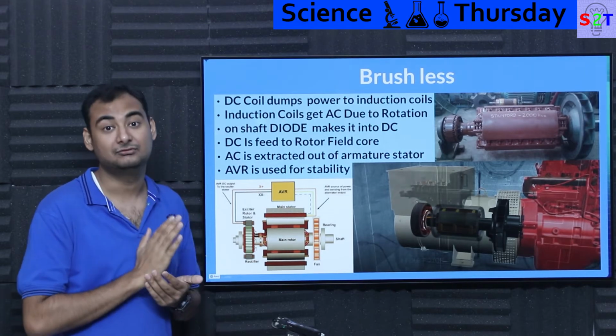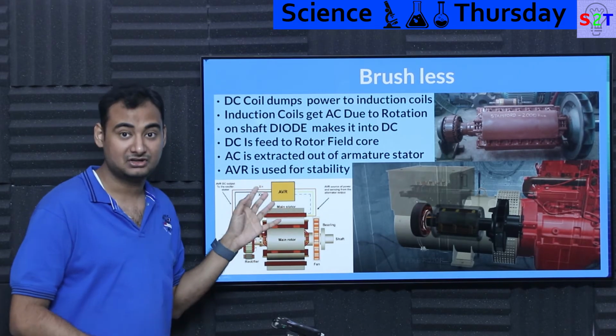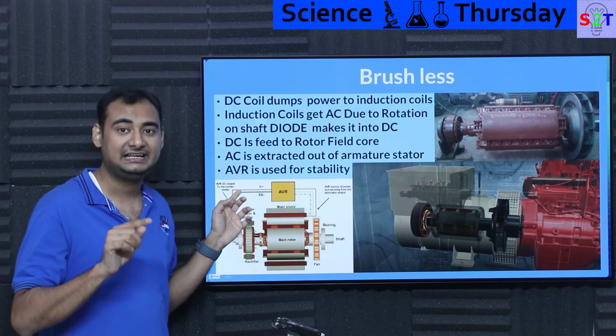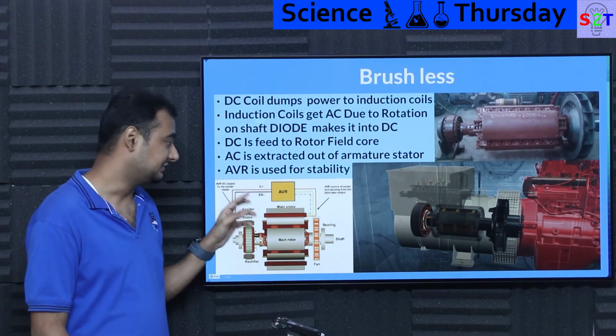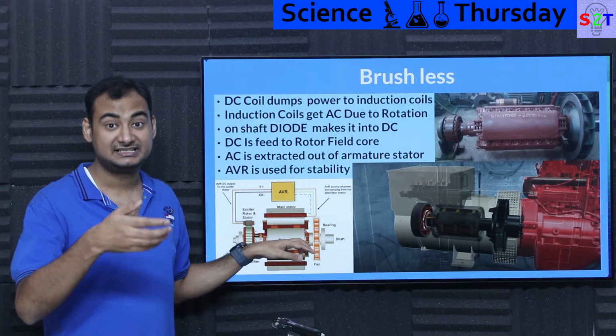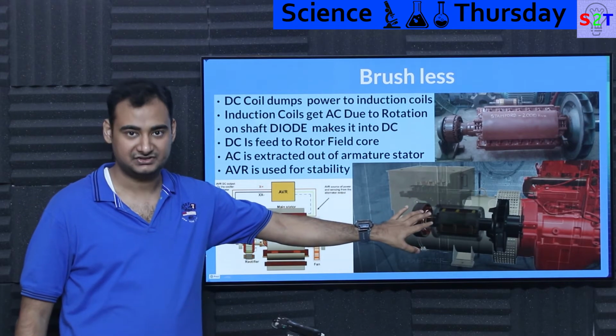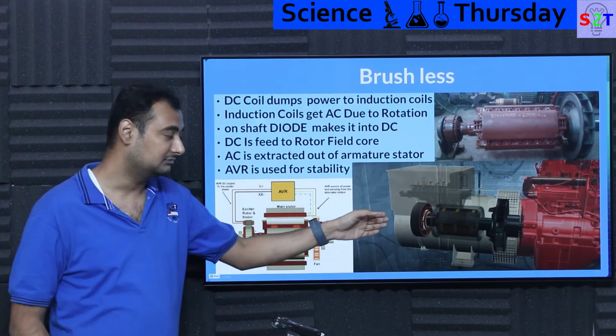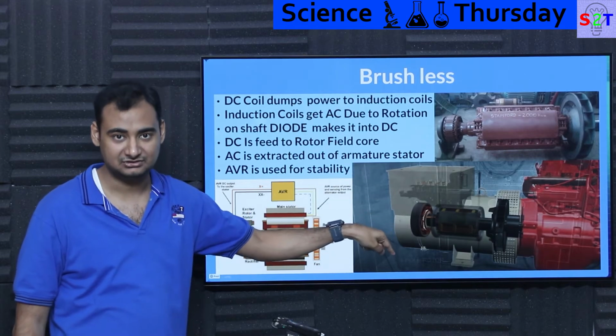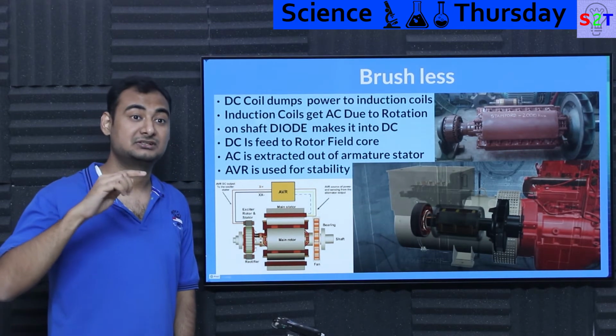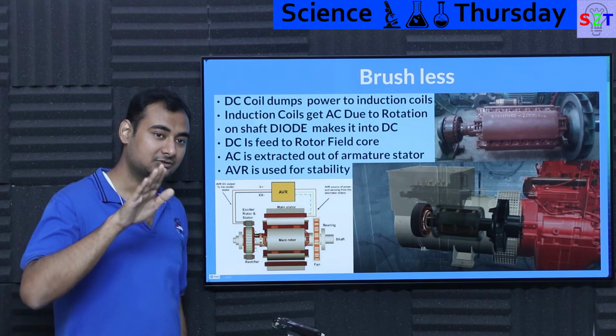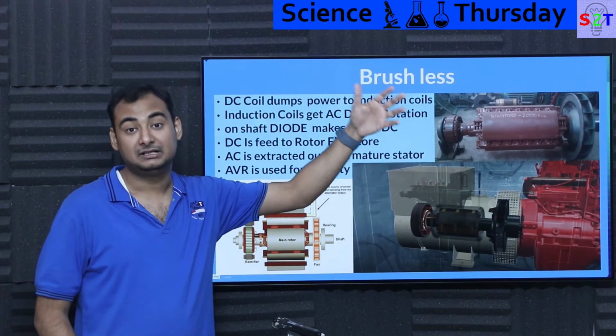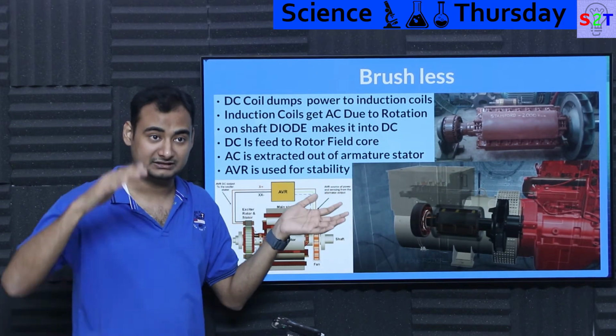You can monitor the voltage, and that's why these brushless generator systems utilize what we call AVR, automatic voltage regulation. It studies what's coming out of the generator section, and based on that, it modifies the DC being sent into the system. If voltage is going up because there's no load, it calms down the exciter current. Then, if you put some load and the voltage starts to sag...